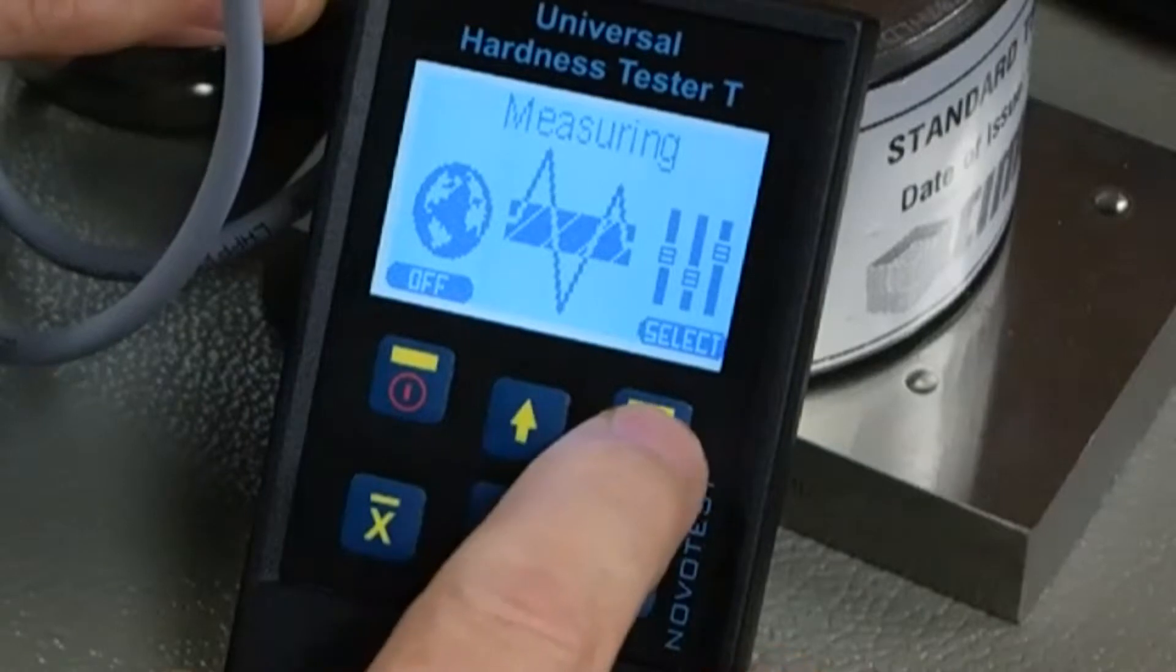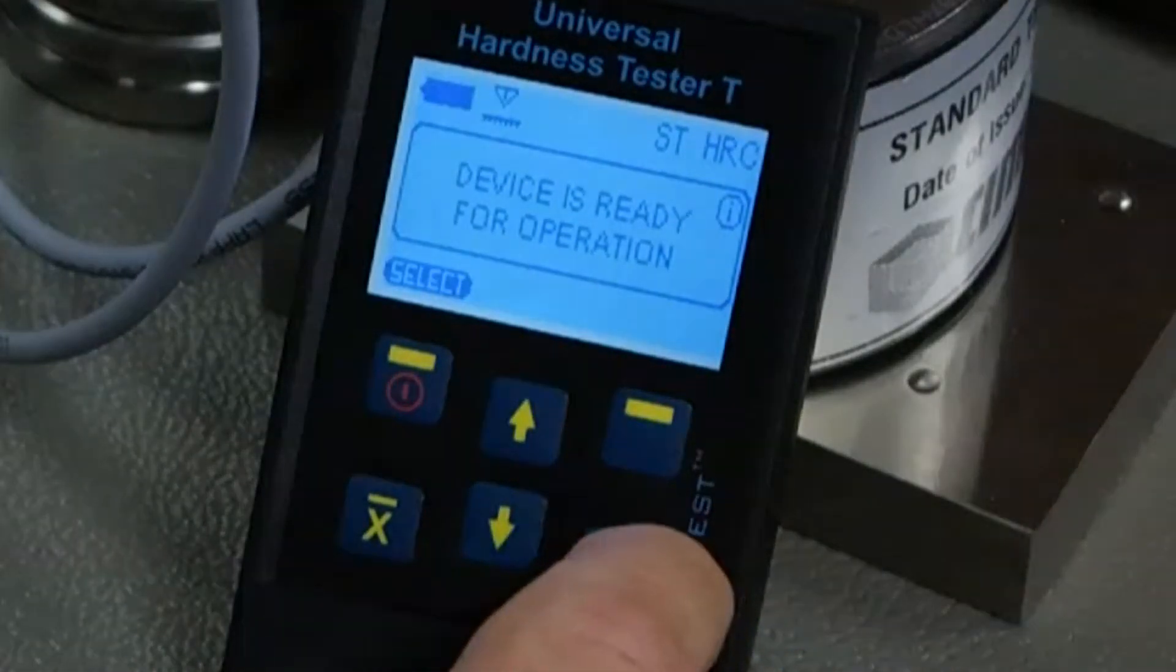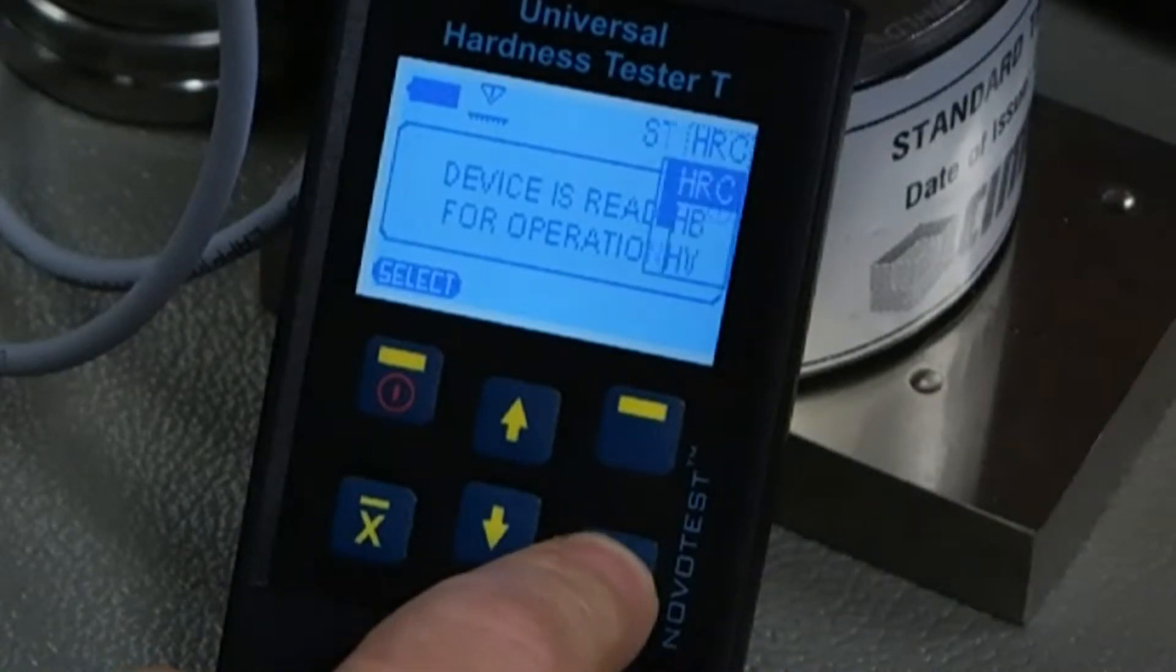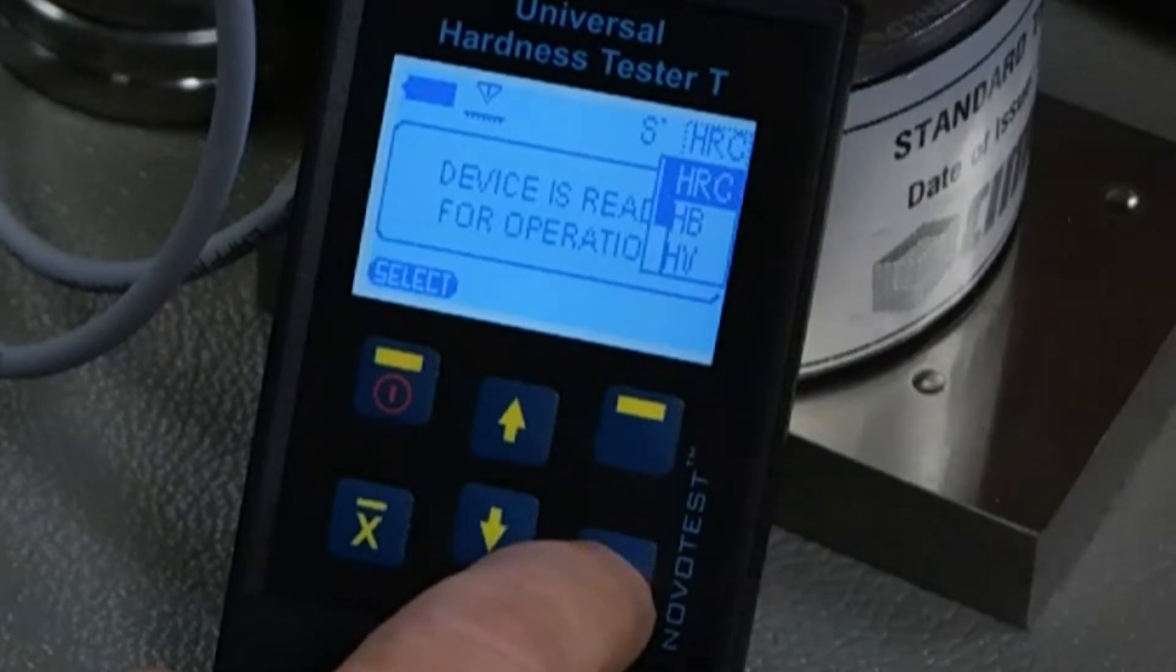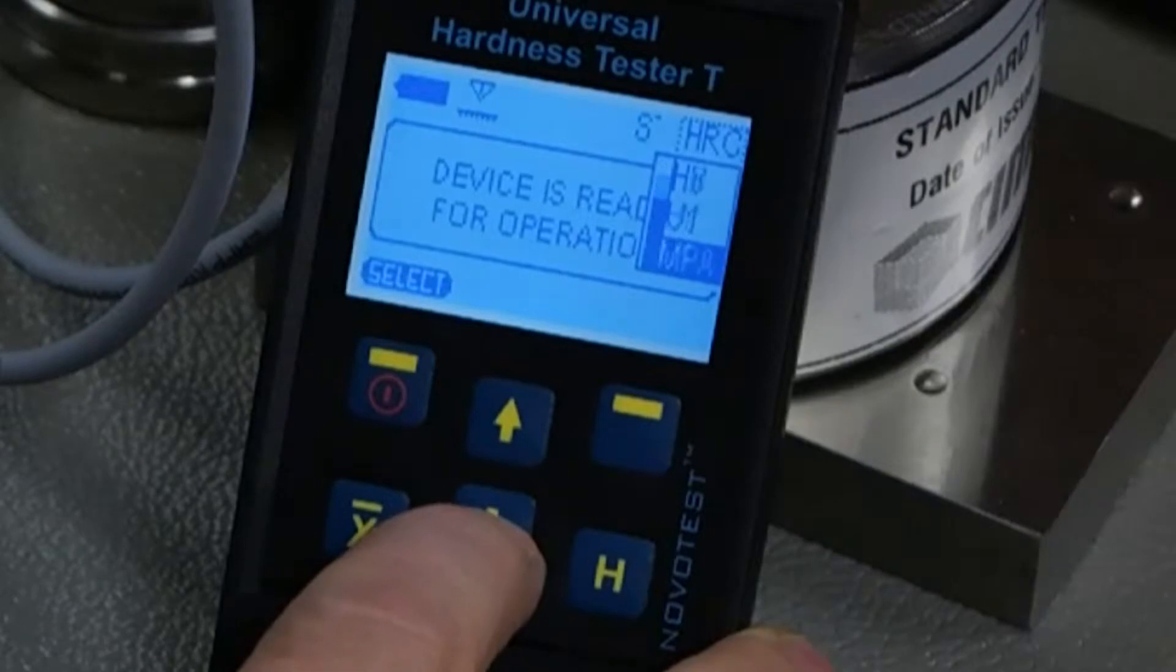If we go back to measuring and hit the select button, the device now is saying it's ready for a test. I can hit the H value button and change the hardness value for HRC and HB, and then in Vickers. I can scroll down these to choose a different one, even user definable.